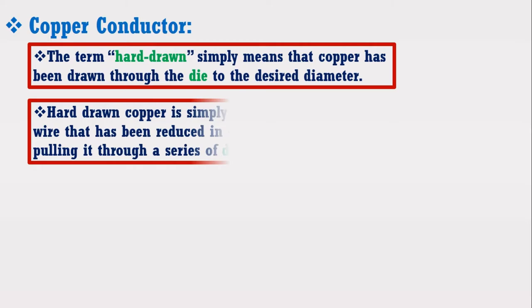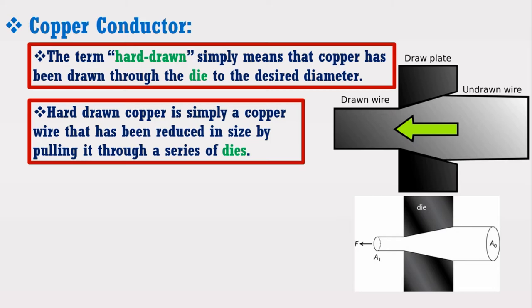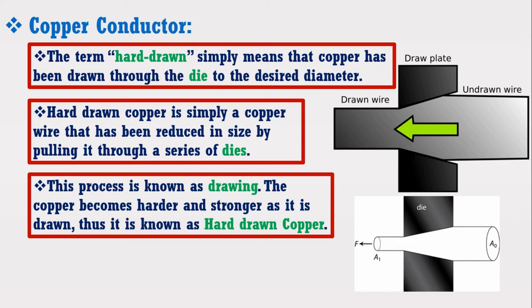In other words, hard drawn copper is simply a copper wire that has been reduced in size by pulling it through a series of dies. Different dies can be used to reduce the size of the material to a desired diameter and shape. This whole process is known as drawing. The copper becomes harder and stronger as it is drawn, thus it is known as hard drawn copper. The copper conductor is passed through the hard drawn process in order to increase its tensile strength, which is an important requirement for a conductor material used in overhead transmission lines.